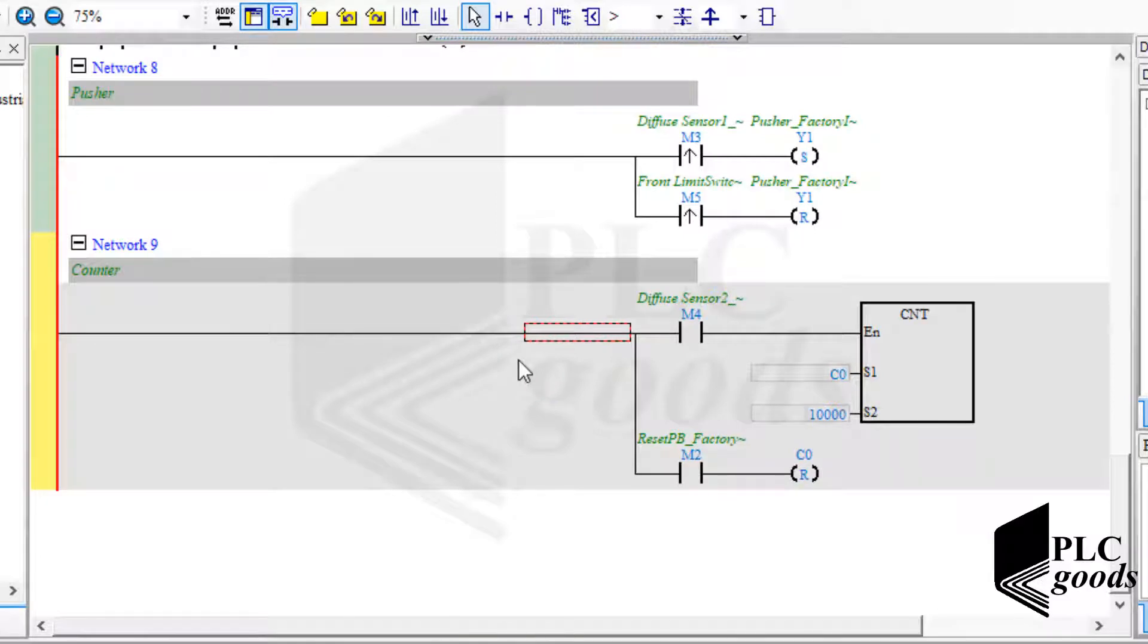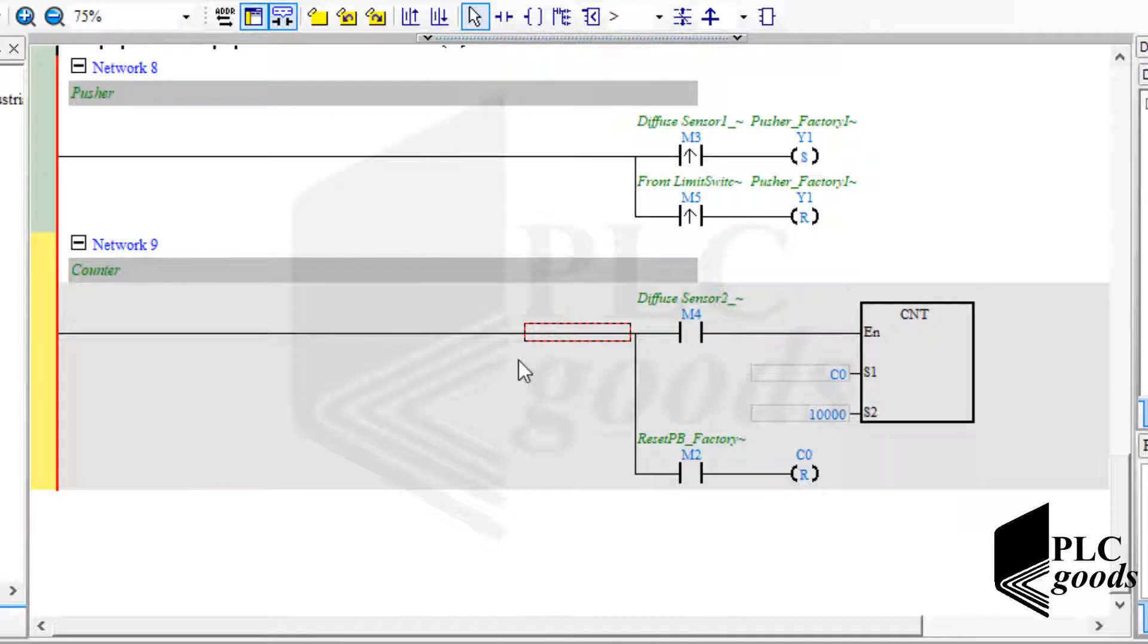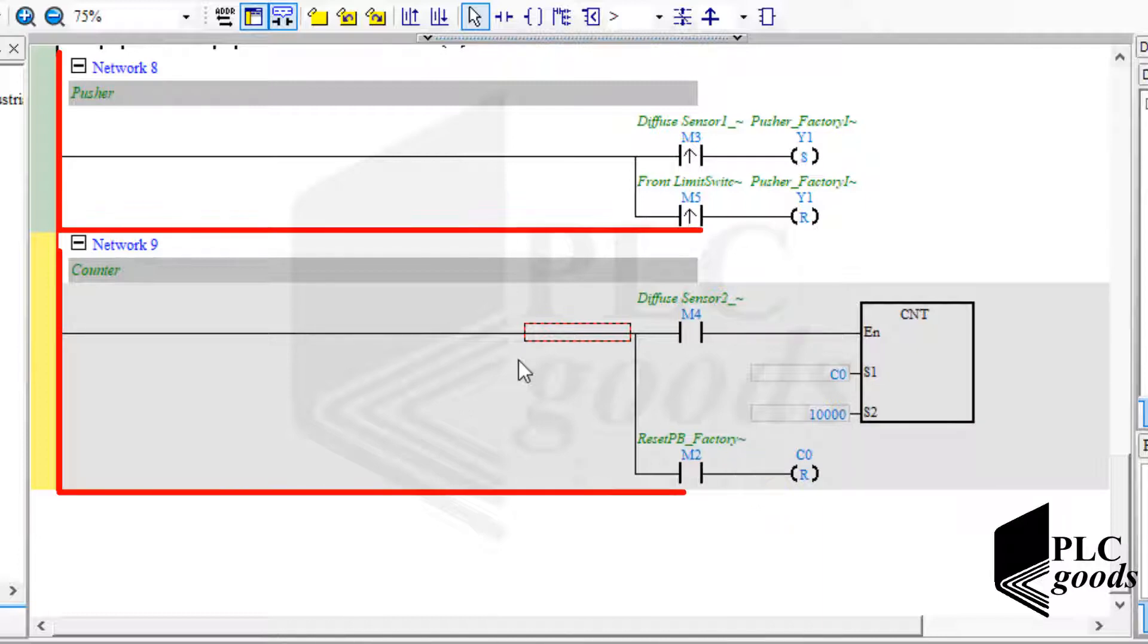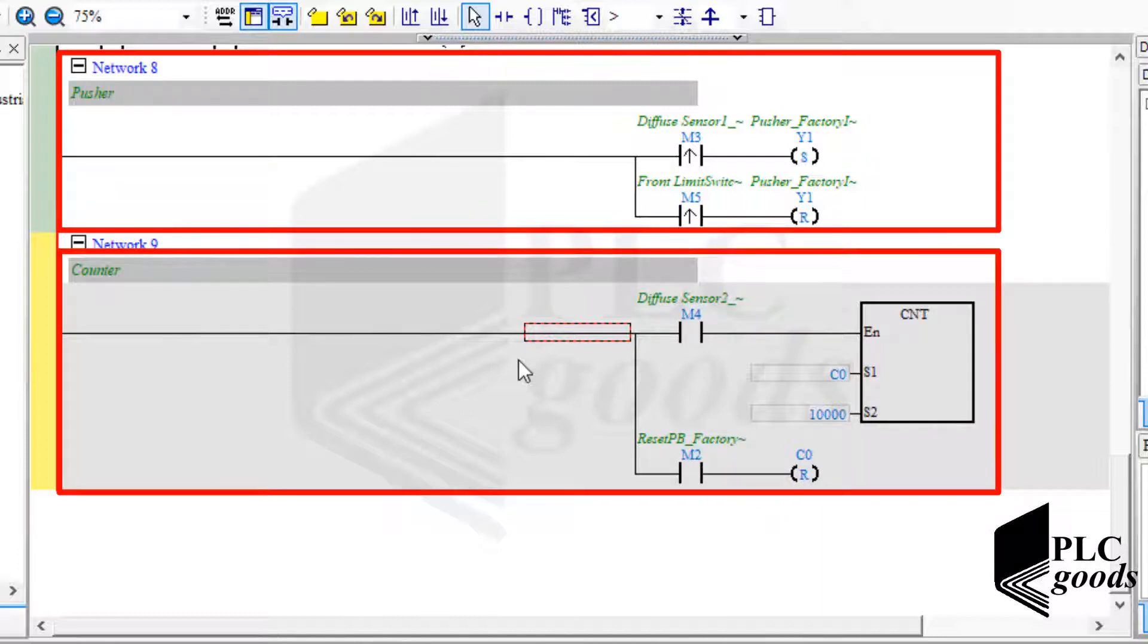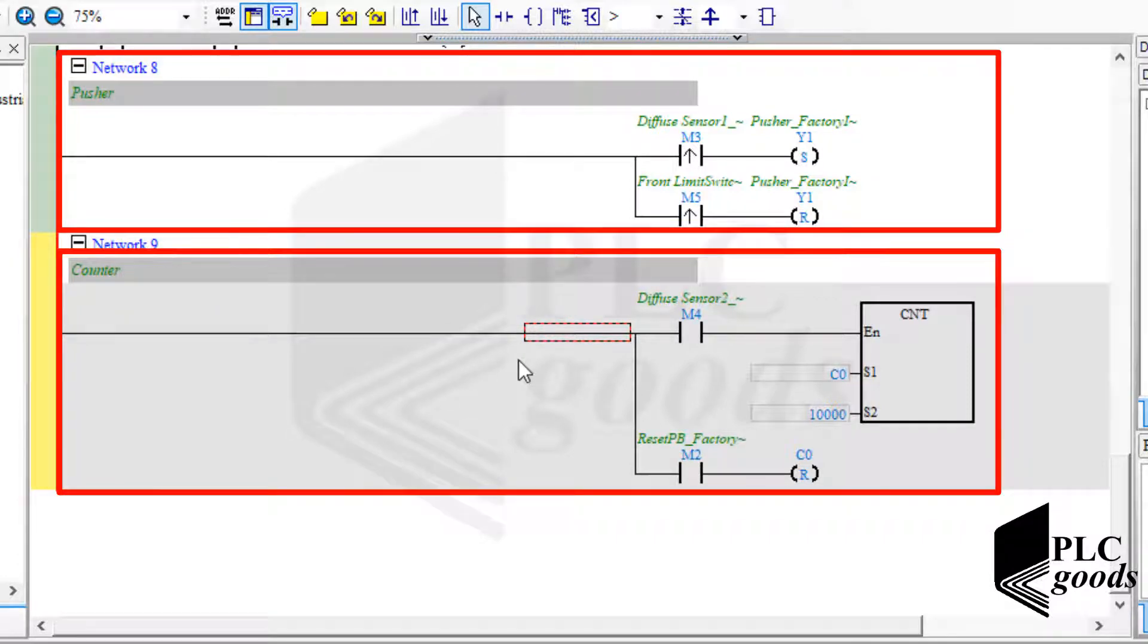As you see, I've connected the second sensor to this counter. So it will count all boxes. After that, I've used the reset push button to change the counter value to 0. Note that usually try to use a separate network for each output, because PLC updates its all outputs after the whole program is executed.